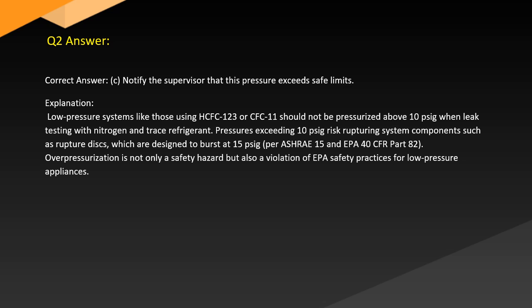Answer. Correct answer: C. Notify the supervisor that this pressure exceeds safe limits. Explanation. Low-pressure systems like those using HCFC-123 or CFC-11 should not be pressurized above 10 psig when leak testing with nitrogen and trace refrigerant. Pressures exceeding 10 psig risk rupturing system components such as rupture discs, which are designed to burst at 15 psig per ASHRAE 15 and EPA 40 CFR Part 82. Overpressurization is not only a safety hazard but also a violation of EPA safety practices for low-pressure appliances.